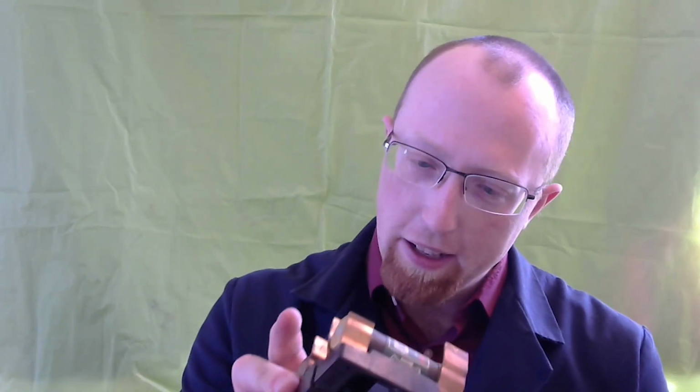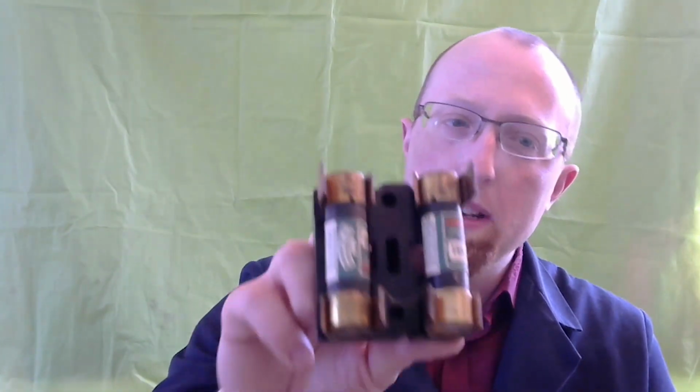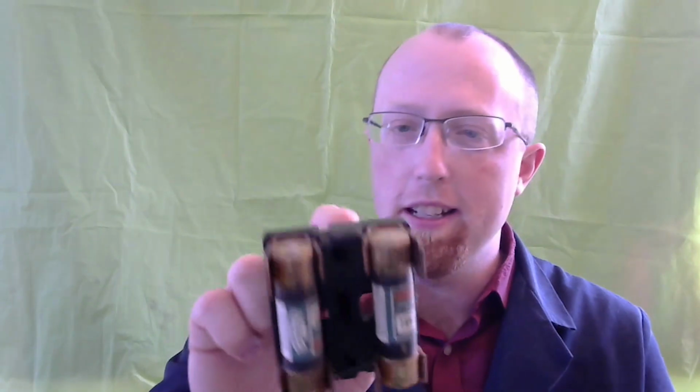And other ones, I found these in my basement, so I'm not sure how old they are. Here's another one that is 60 amp. This is a pretty big thing. It has a pull out plug thing. It just says pull fuses. These were designed to be the part of the circuit that failed so that you could get to them. Nowadays, it tends to be more circuit breakers, where when too much current is pulled, it flips a switch. That way you can just go back and flip the switch back, and you don't have to replace these. But same idea: the weakest part of the circuit will break when too much current is drawn, and it's something that we can get to readily.